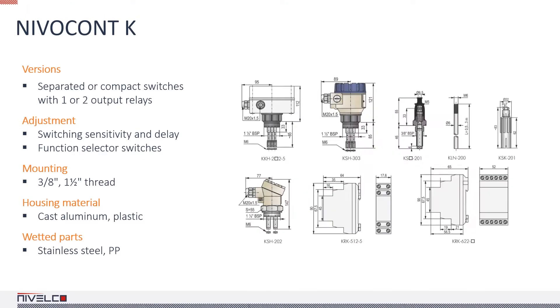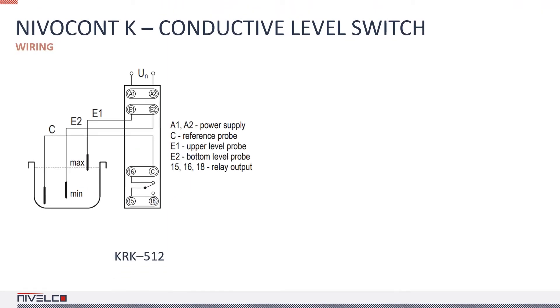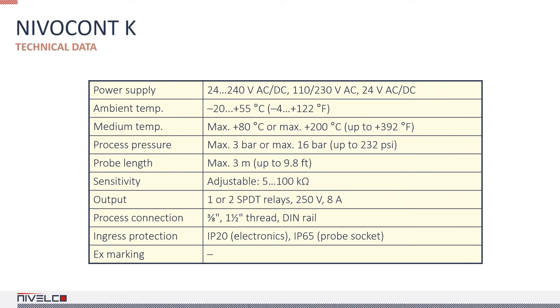Nivocont level switches have detached and compact versions. The compact variant is designed so that the housing of the electronics holds one or two signal processors, and the probe socket is at the bottom of the housing. In the case of the detached version, only the probe socket is installed in the tank, and the signal processor is usually placed in the control cabinet. These are the typical wiring diagrams for the single and dual channel versions. With the dual channel version, two independent level switches can be created. The single channel version can be ordered with many different power supplies depending on the application and user requirements, while the dual channel version has only three types of power supplies.